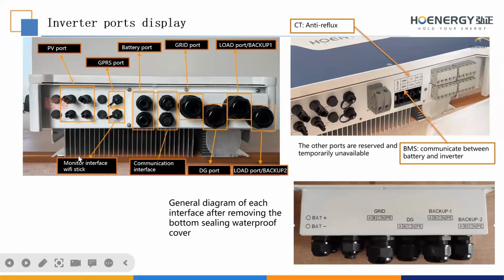Take a look at the first picture. From left to right, this is the PV interface. We have two MPPT modules, so we can connect two PV modules into the inverter. This is the GPRS interface, and here is a Wi-Fi interface. This is the battery interface, communication interface, grid, DG, and EPS load interface. DG means diesel generator.